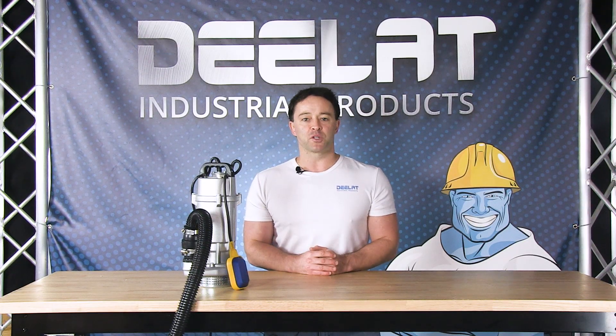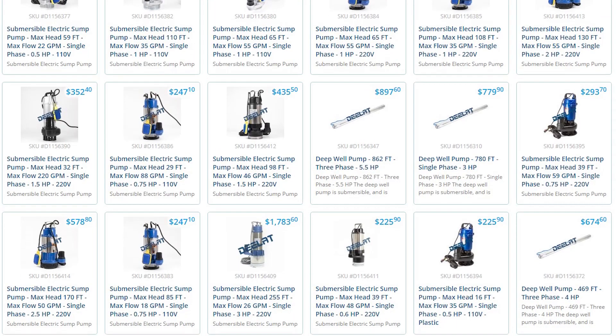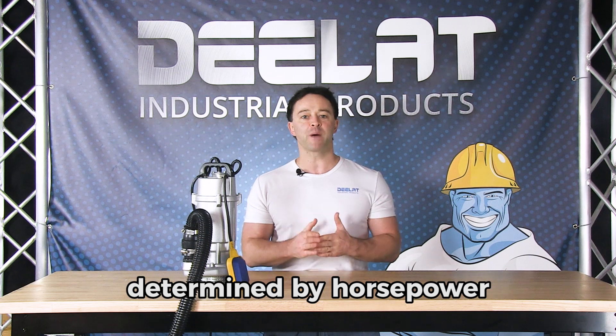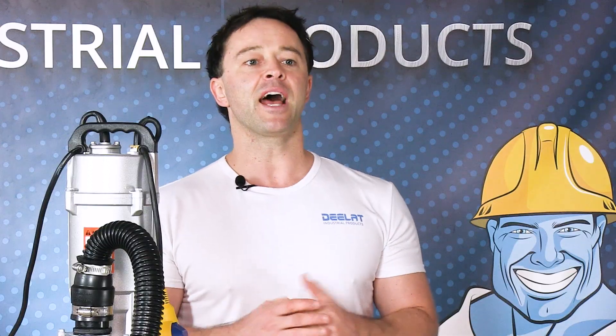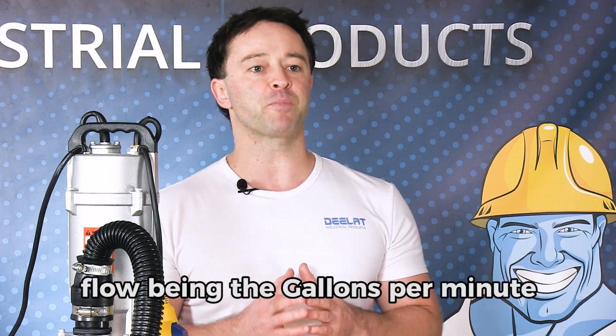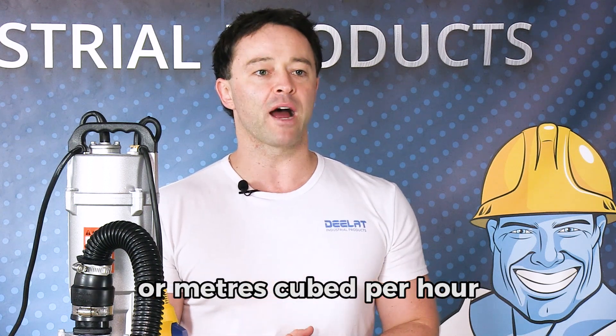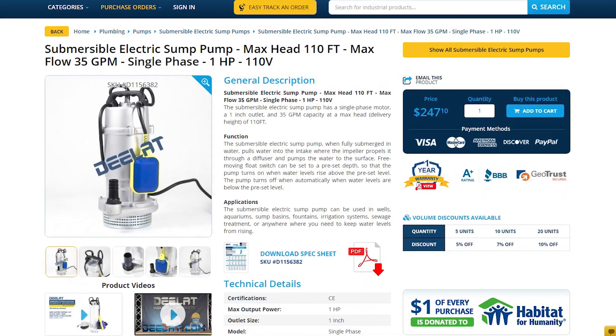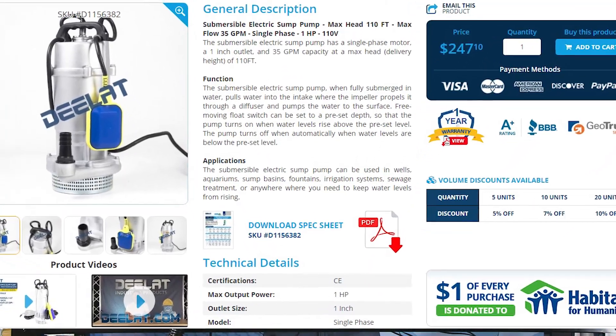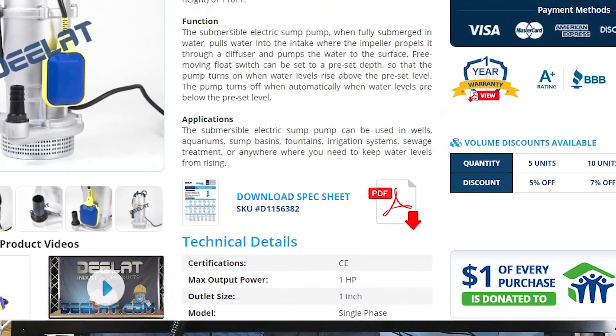Deelat sells a variety of submersible pumps that have a range of pumping capacity, determined by horsepower, resulting in different flow at different head heights. Head height being the depth at which your pump is installed, and flow being the gallons per minute or meters cubed per hour that can be output at that height. You can find the head height or flow chart on the product page in simple PDF formats, which will help you determine if the submersible pump is suitable for your application.